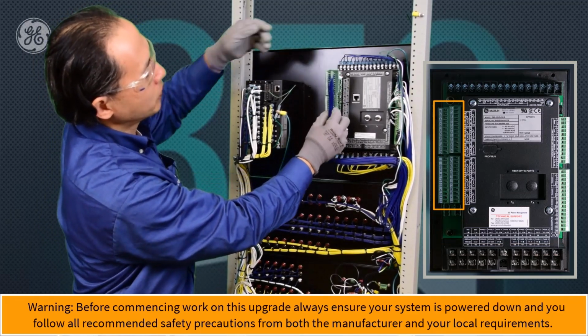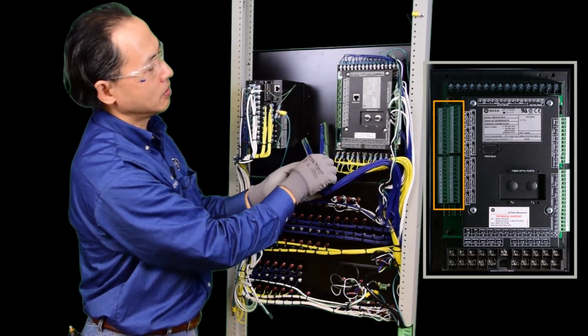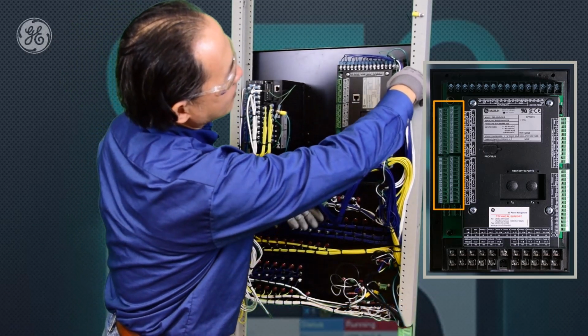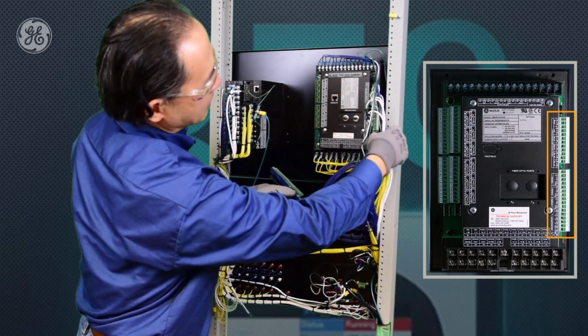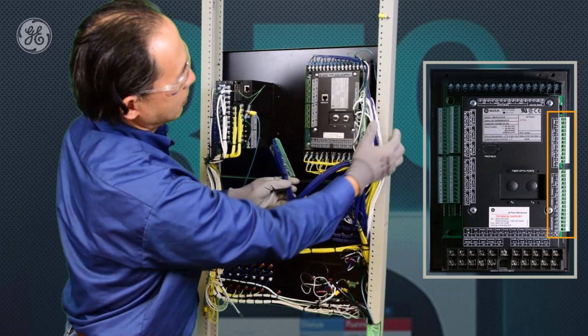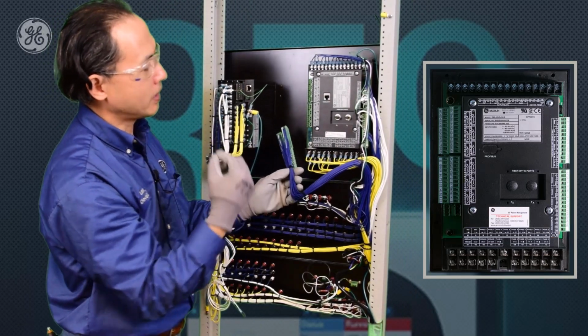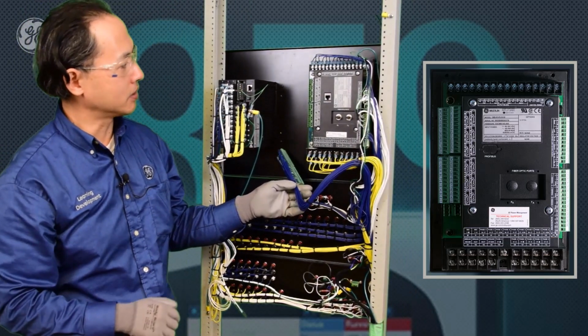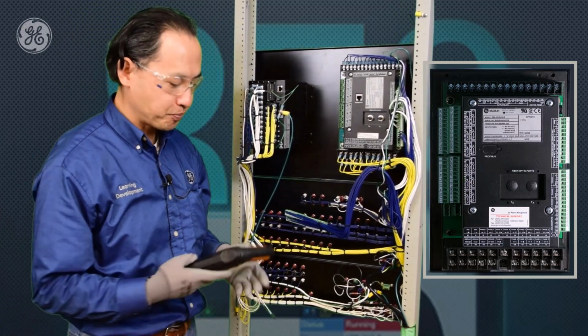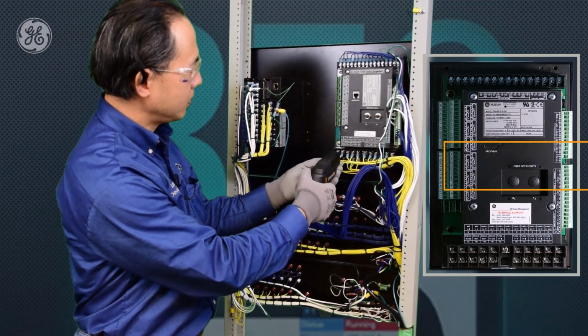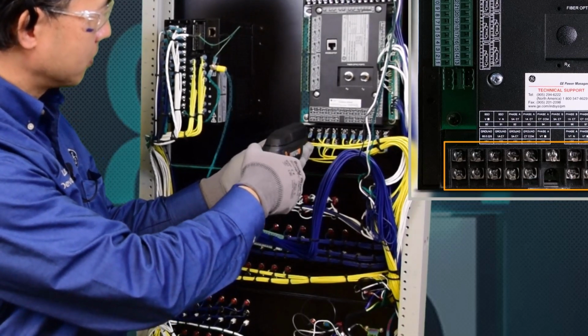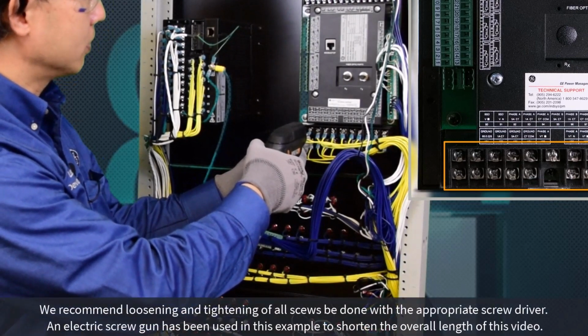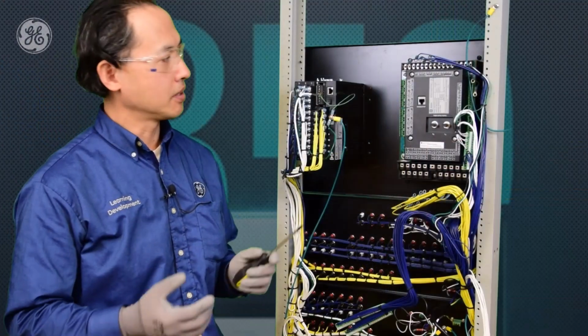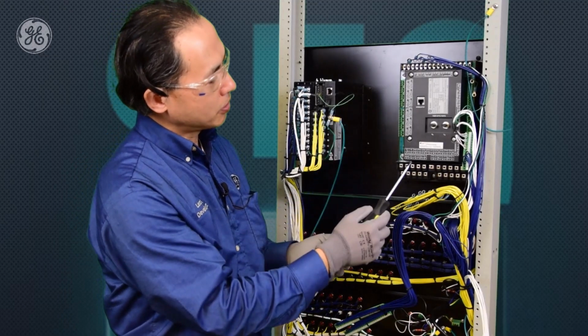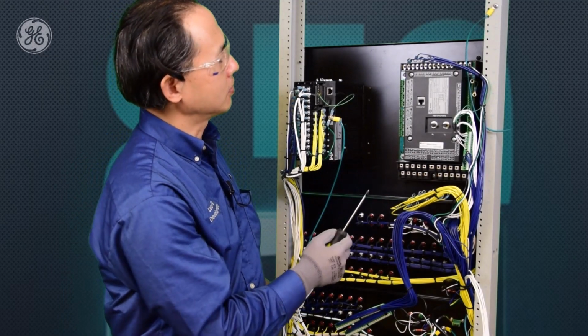For these terminal blocks, we can just unplug them without rewiring the wire on the terminals. And on the left side, we have the digital inputs and the communication ports. So these can be just directly unplugged, and later we can plug them into the 859. And now for the CT-VT inputs at the bottom, we can just use a screwdriver to manually remove the screws. So now we removed the top and the bottom wiring and unplugged the terminal blocks on the right.